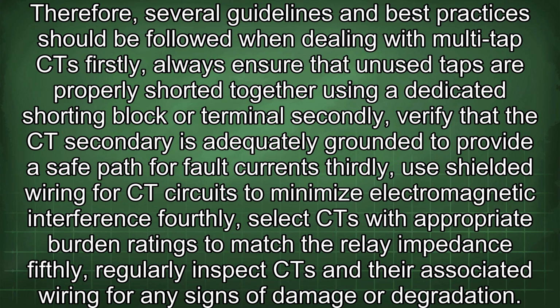Therefore, several guidelines and best practices should be followed when dealing with multi-tap CT. Firstly, always ensure that unused taps are properly shorted together using a dedicated shorting block or terminal. Secondly, verify that the CT secondary is adequately grounded to provide a safe path for fault currents. Thirdly, use shielded wiring for CT circuits to minimize electromagnetic interference. Fourthly, select CT with appropriate burden ratings to match the relay impedance. Fifthly, regularly inspect CT and their associated wiring for any signs of damage or degradation.